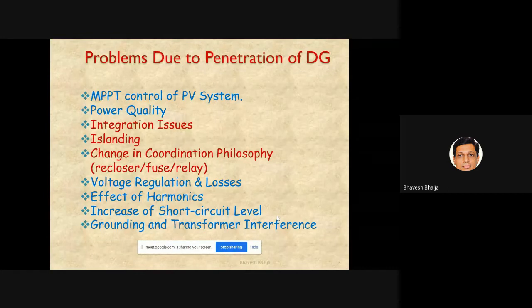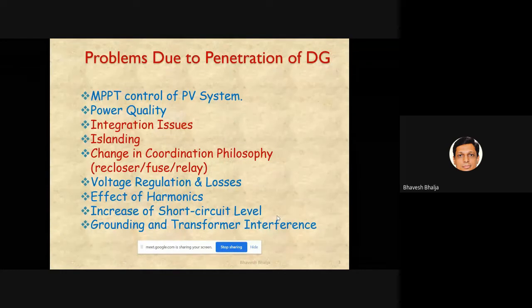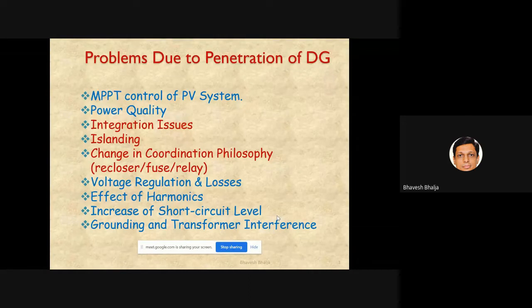So if I reclose after some time, there are some standards for that also, right? So 0.3 second is the waiting time period. After 300 milliseconds, if I reclose the circuit breaker and the fault is not there, my system is healthy. There is no need to send the lineman for maintenance and so on, right? There is no manual closing of the circuit breaker required. Nothing is required. But when you connect DG with such a system, whether at distribution or transmission level, then the coordination becomes very difficult, right? Because of the bidirectional power flow from any direction, right? Either both directions or multiple DGs are also there.